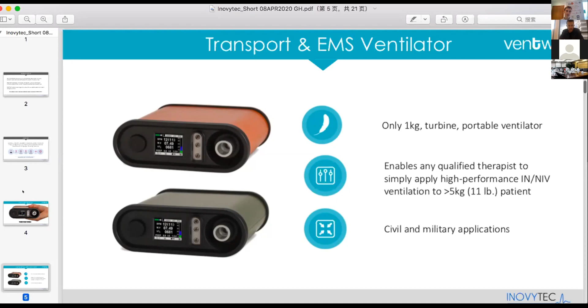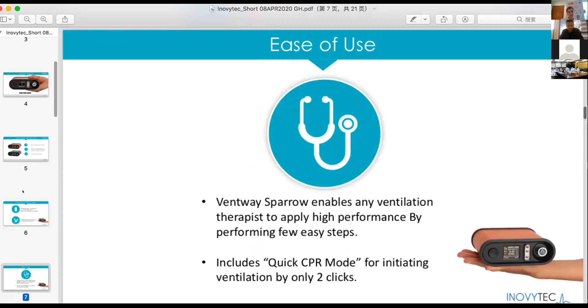The characteristics of the ventilation, if you can scroll down to the next slide. One more. Yeah, so the characteristics of the ventilation, as you can see, are high spec. We're talking about 4 modes of ventilation, both volume control and pressure control, SIMV, including also CPAP mode. Very high tidal volume, up to 2 liters. And as you can see, in general, this ventilator can serve almost any patient, both out of the hospital and in hospital. The ventilator also supports invasive and non-invasive ventilation, and also incorporates leak compensation in a very, very efficient way. I will just give you a half-a-minute background about the usage so far.